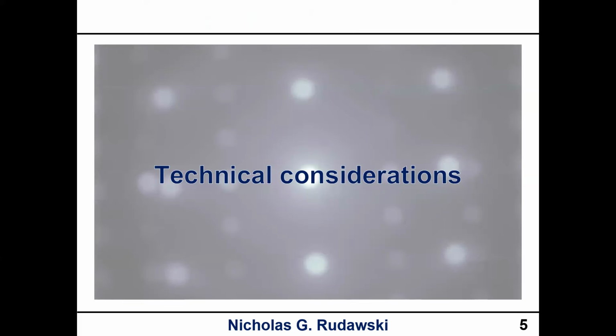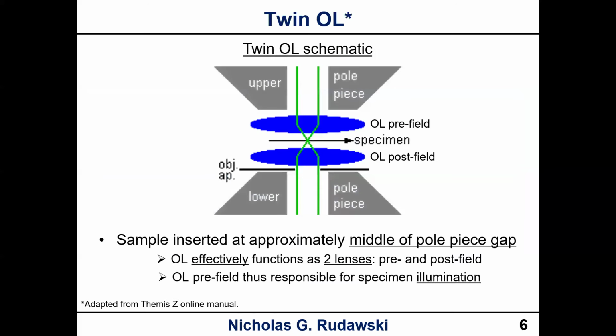So if we talk about the technical considerations, on current state-of-the-art S-TEMs, they have a twin objective lens design. This was a schematic that I adapted from the Themis Z online manual. You have an upper and a lower pole piece, and you insert the sample at approximately the middle of the pole piece gap. So in this case, your objective lens functions as two lenses, a pre-field and a post-field. Sometimes you also hear these referred to as upper and lower objective lens. But in this case, we're concerned with the pre-field because that is the last lens that the beam sees before it illuminates the sample. So that is responsible for specimen illumination.